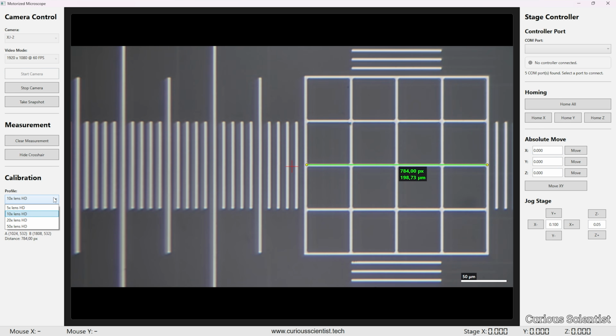Plus, it is important to mention that these calibrations are only valid for a Full HD image feed. For 4K, I would need to do another set of calibrations, because there would be twice as many pixels between the same points as for the Full HD image. So a line with, let's say, 500 pixels length would represent a different distance in millimeters at Full HD resolution than at 4K resolution.